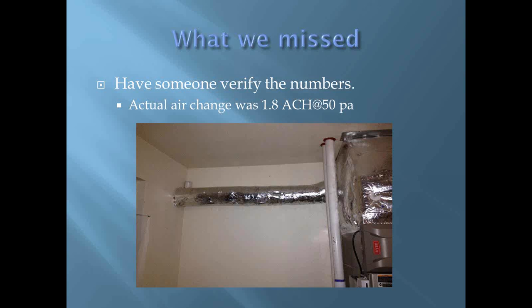I don't understand that calculation you just said. What is this? Well, the idea was, if somebody used a square duct instead of a round duct, how would they size it? So what I would have preferred, it says, was the 6 inches good up to 1,600 square feet and 8 inches good up to about 2,700 square feet. Typically, if you go more than that, you're going to have multiple furnaces. You can put one on each one.